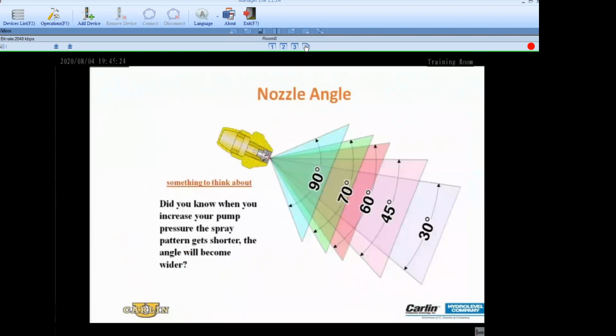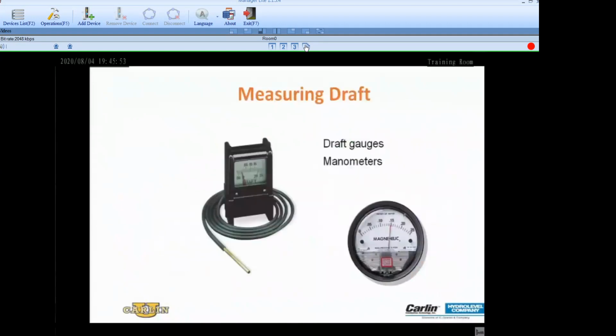So you can't have the air pattern of the burner coming out at a 70-degree angle and put a 45-degree nozzle. Or you can't have a 45-degree air pattern and put a 90-degree nozzle in there. It has to be a good match, and not mixing the air properly with that atomized oil, then you're going to have more excess air than needed, and you're not going to have good combustion.